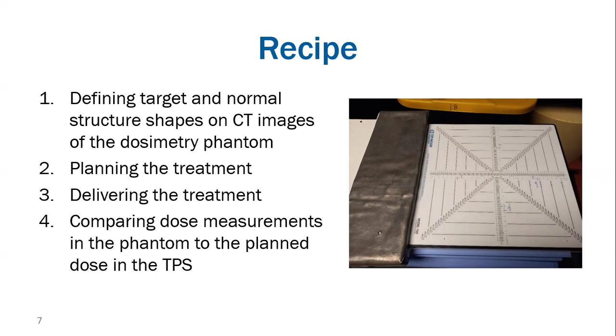You then plan a treatment plan using IMRT, or if we're talking about VMAT later in the talk, using VMAT. You then deliver the treatment with a measurement device, whether it's an array detector or some number of point detectors. And then the idea is that you want to compare the dose that you measure in the phantom during the delivery to the planned dose at that same point in the TPS. And you can do this, like I said, either by comparing point doses, or in an array manner where you actually perform gamma analysis on this.